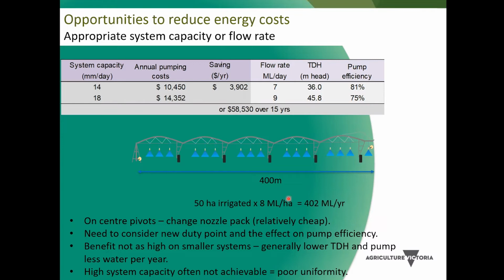The benefits of doing this are higher on big systems. As systems reduce in size, generally they have lower pressures in the first place, but also you're pumping less water per year. So the benefit's not quite as large.